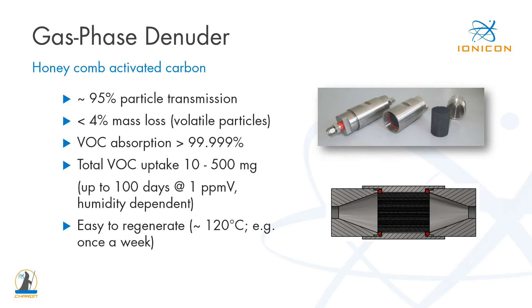Let me add some details to the individual parts of CHARON. The gas phase denuder consists of honeycomb activated carbon that transmits more than 95% of the particles and at the same time shows less than 4% of mass loss even for volatile particles. Volatile organics are efficiently absorbed — typically more than 99.999% are removed. In addition, the gas phase denuder can be in continuous operation for several weeks. Once the activated carbon starts to show saturation, it can easily be regenerated in-system by heating it to 120 degrees Celsius for a few hours.